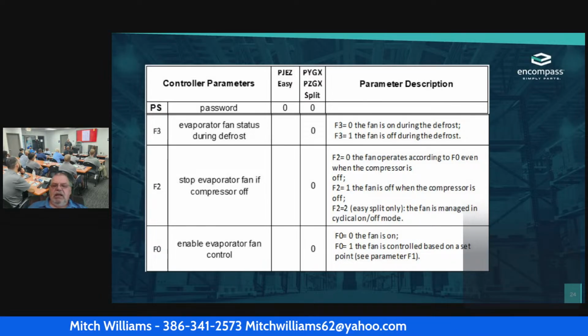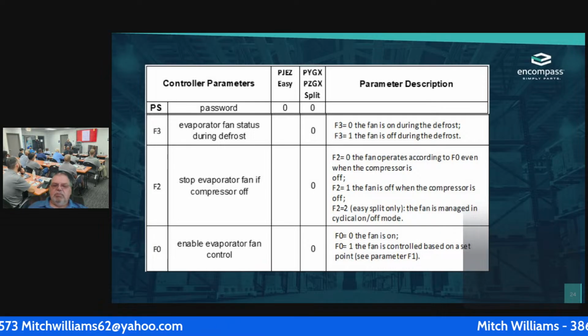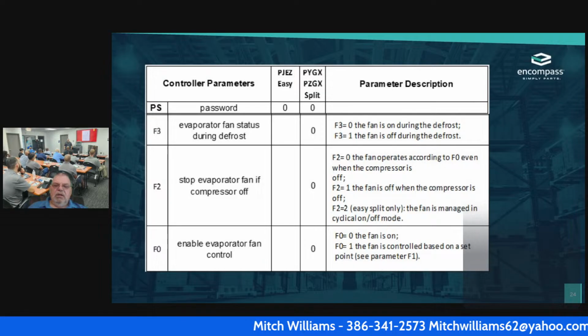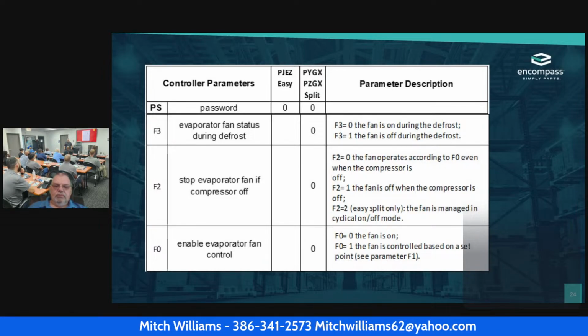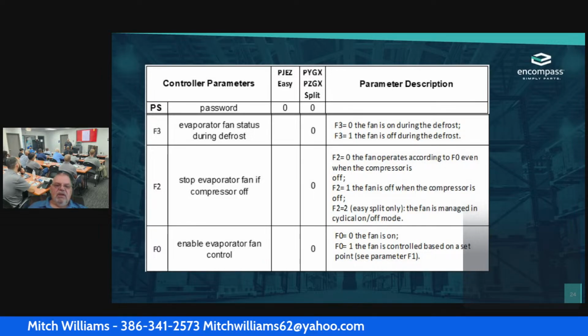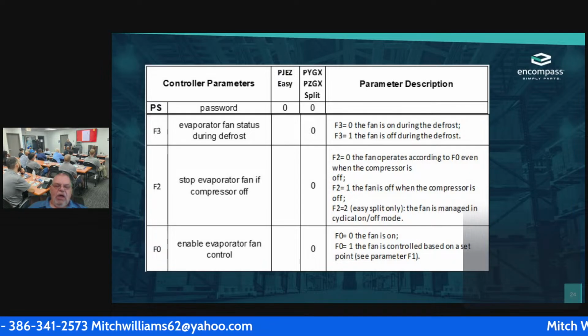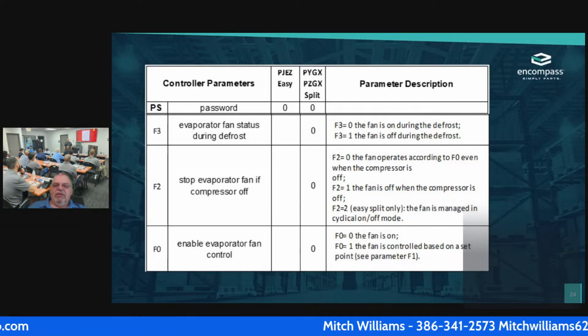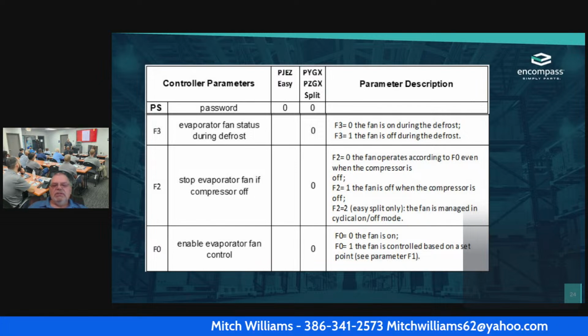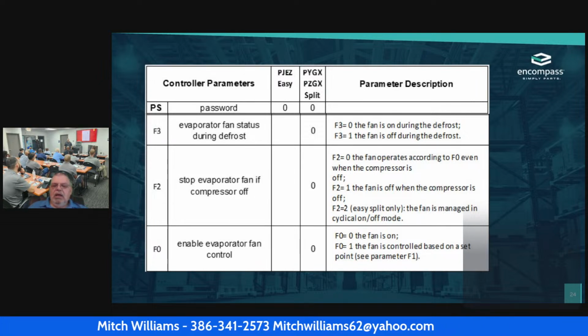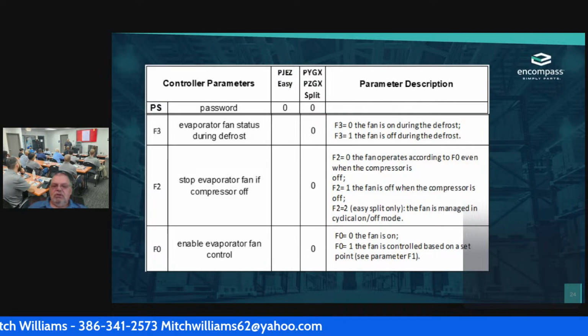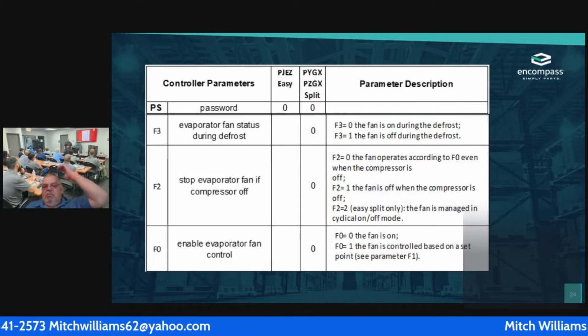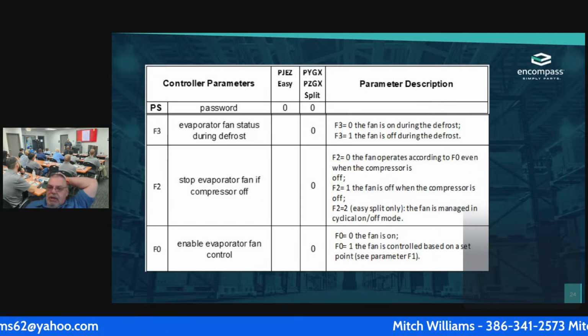And then if I get an F2, the easy split only, that is the fan is managed in the cyclical on-off mode. Okay. Once I get to the F0 mode, that enables the evaporator fan control. 0 is the fan is on all the time. 1, the fan is controlled based on a set point. And then I have to go back once again. I go to my parameters on F1.